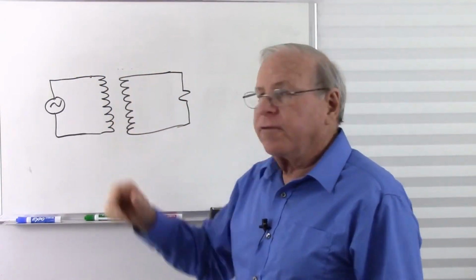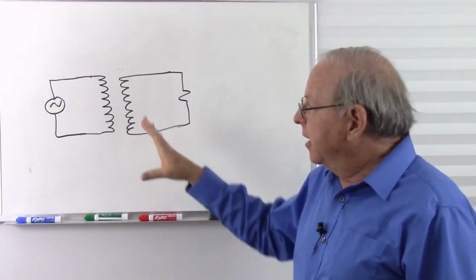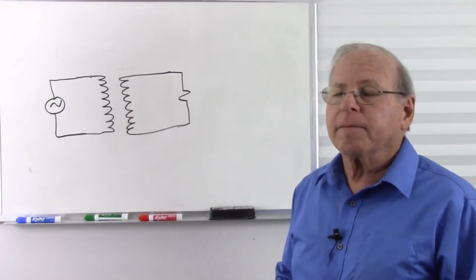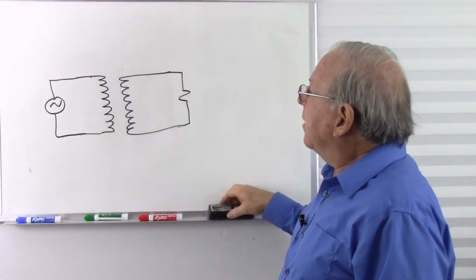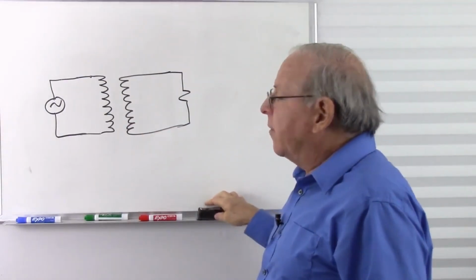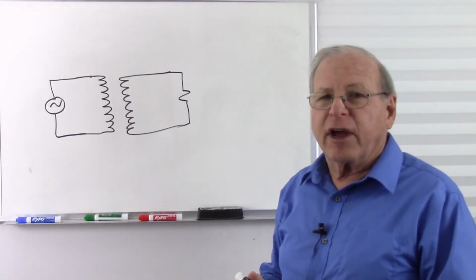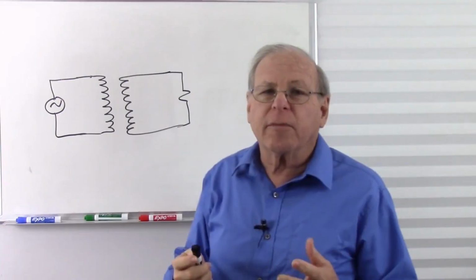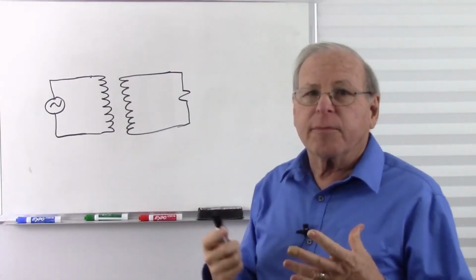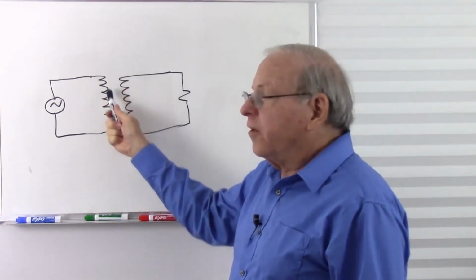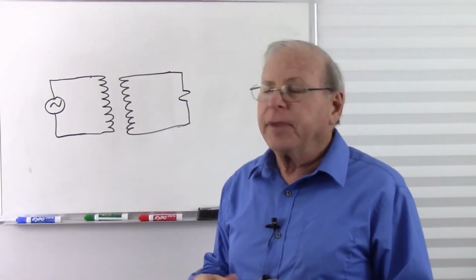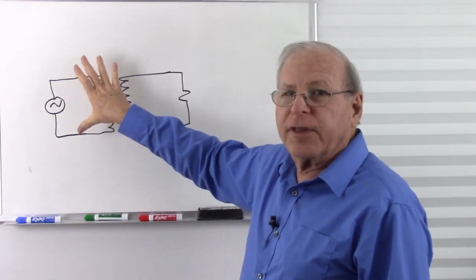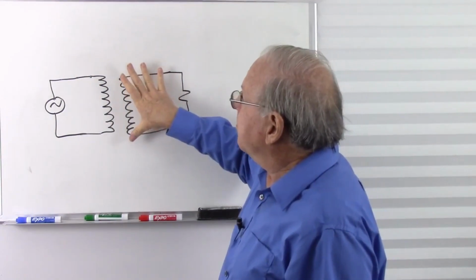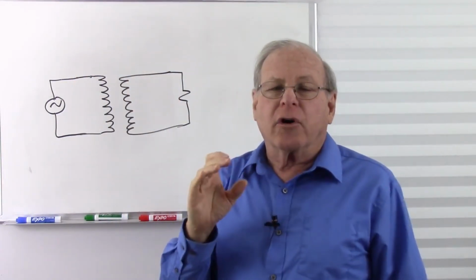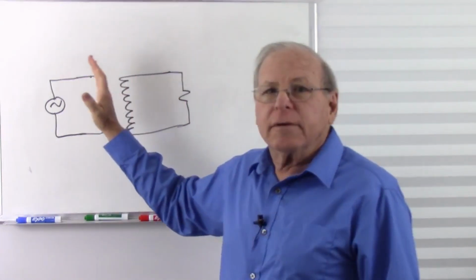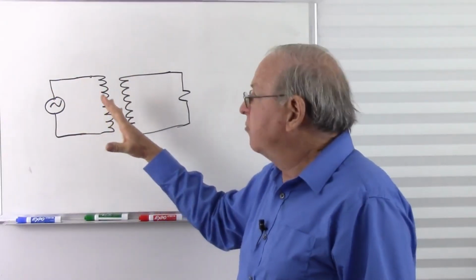So no current can flow one way or the other in a standard transformer. So that's one of the properties that we exploit to make an isolation transformer. Now, an isolation transformer is also enhanced for other properties. For example, we want very good high voltage insulation. So we have insulation that's good for thousands of volts, to minimize any microcurrents that might flow through less high quality insulation.